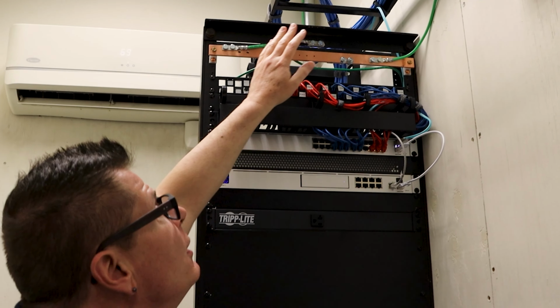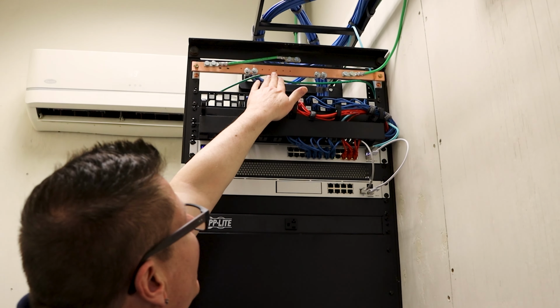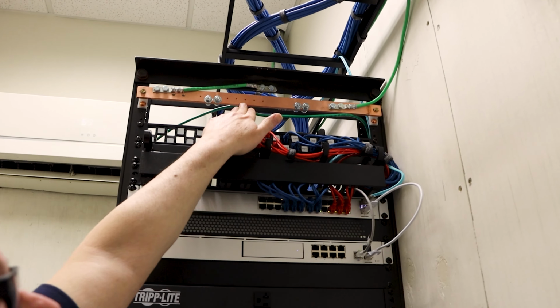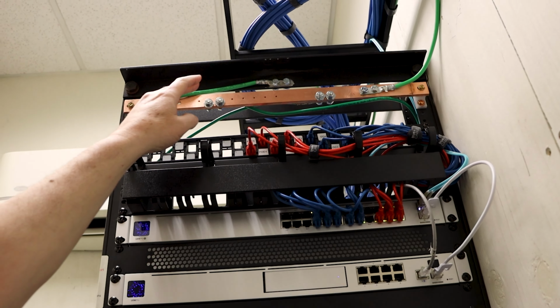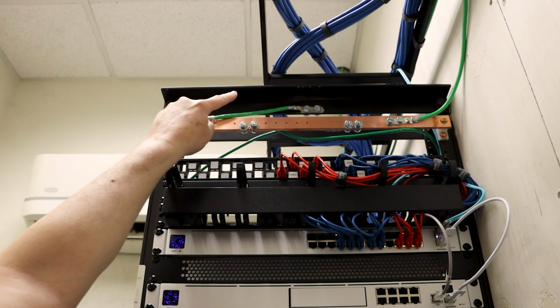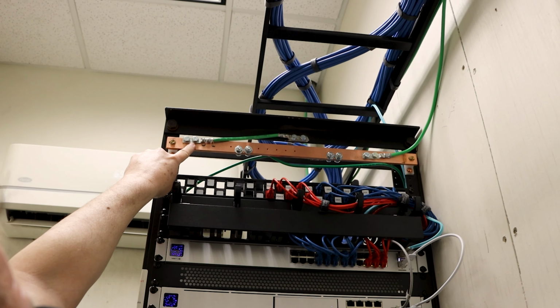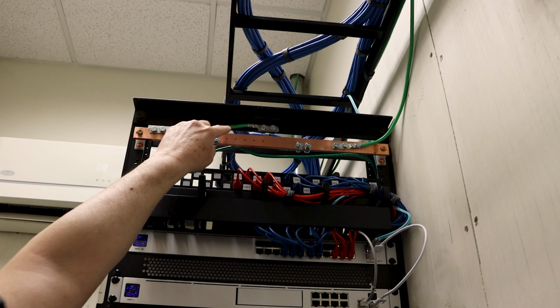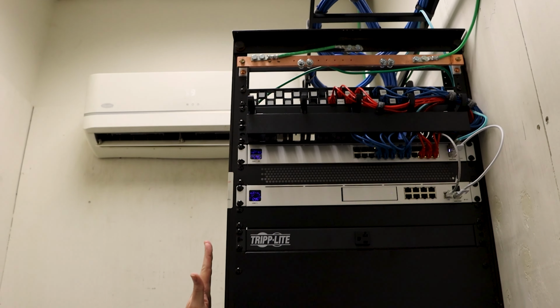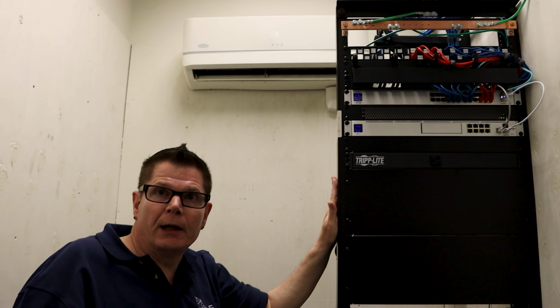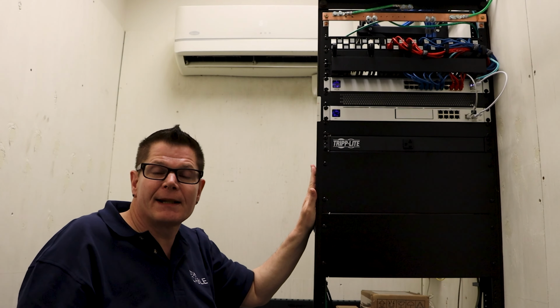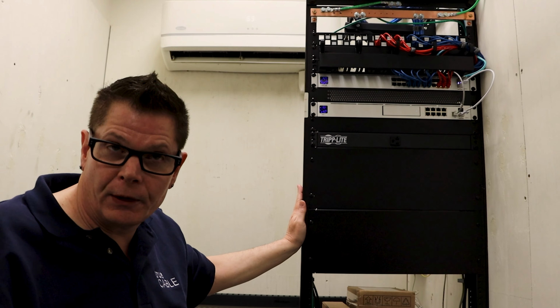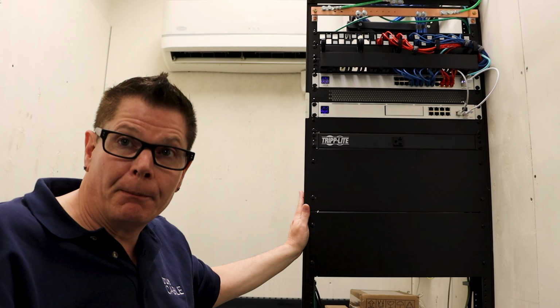So in other words, we've got a copper bus bar that's been mounted to our rack, and everything in the rack, including the rack, is bonded to this bus bar. So for example, we've got a short jumper here, and it's bonded to the rack. One thing that you're going to see on a lot of rack hardware is paint. The paint has to come off. Paint is not a good conductor of electricity. You want to get down to bare metal.